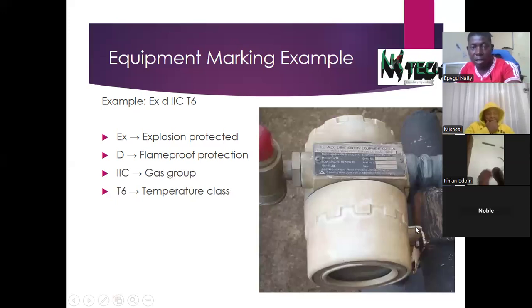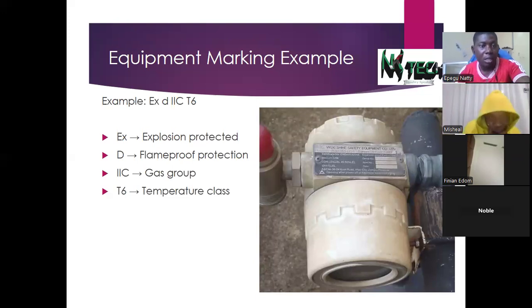Now, this equipment you're seeing here is a fire detector, flame detector, sorry. It is a flame detector. Now, if you zoom into this flame detector, you see this code. You see it right up there, Ex d IIC T6. Let me zoom it in so that we see.